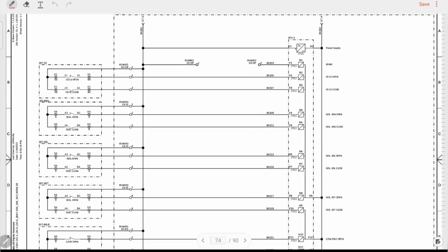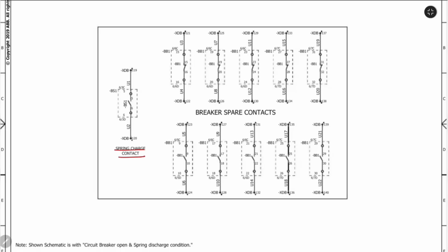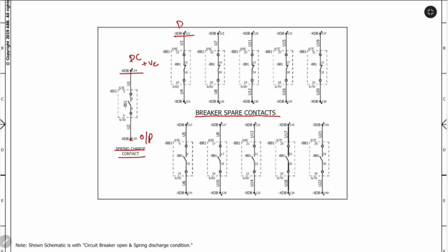Finally, let's wire the breaker status indication so the control room, SCADA, or Bay Control Unit always knows the breaker condition. Spring charged indication, apply DC positive to breaker terminal XDB119. The output from XDB120 becomes the spring charged status signal. Connect this output to the designated digital input on your protection panel. Breaker open indication. Apply DC positive to breaker terminal XDB121.